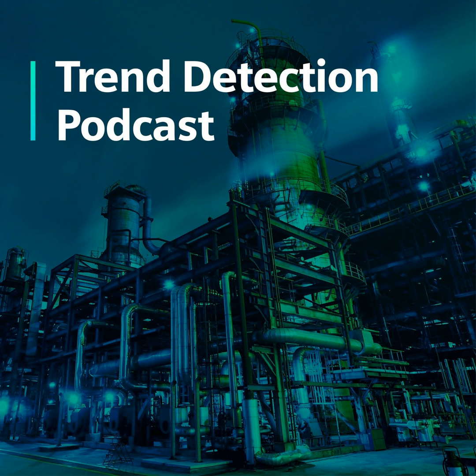Yeah, absolutely. So I think you can't really look at these as a comparison, more as one leads into the other. Condition monitoring is very much a technique of capturing machine-related data that would provide some sort of insight into the condition or the health of the machine. That could be anything from vibration, oil analysis, oil debris data, or the pressures across a pump, and effectively tracking that over time in some way, either periodically using a handheld device or online and continuously monitoring.